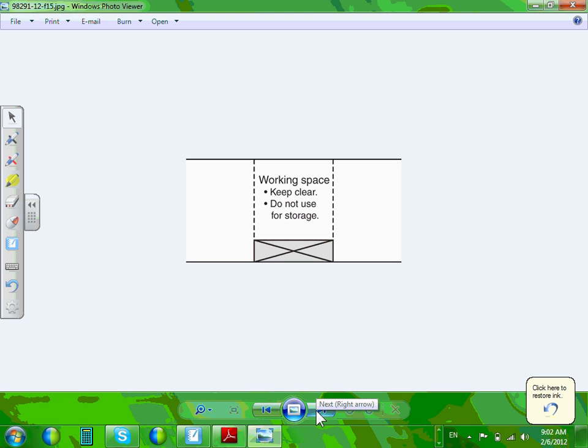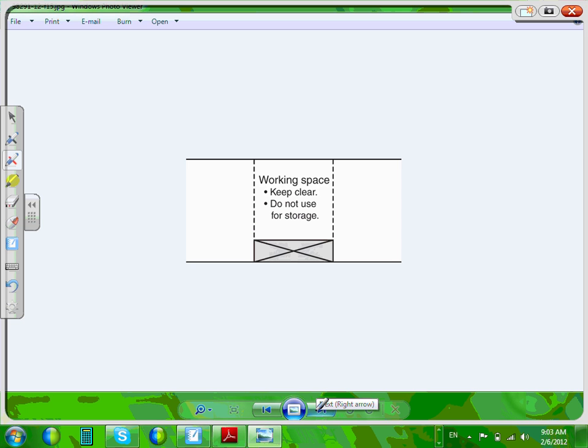A couple of things, housekeeping, guys. Working space, keep clear, do not use as storage. This one right now is a violation of the code. Now, moving this one this way, we're not violating the code. But I always, this is exaggeration, guys. What they don't want you to do, see that bookshelves there? They don't want you to put the bookshelves right in here. That's a violation of the working space for the equipment. But anything movable, you're not supposed to use for storage.